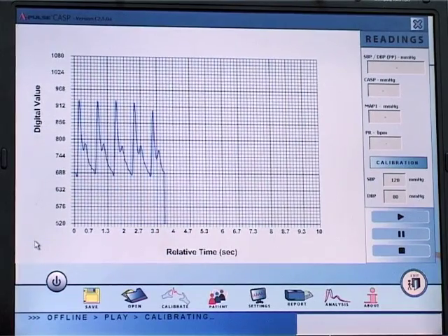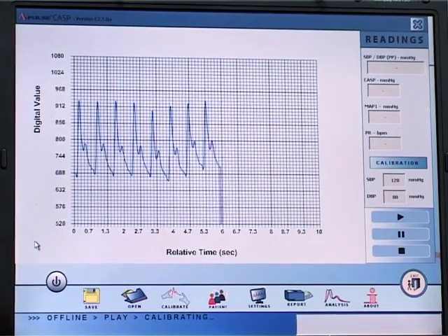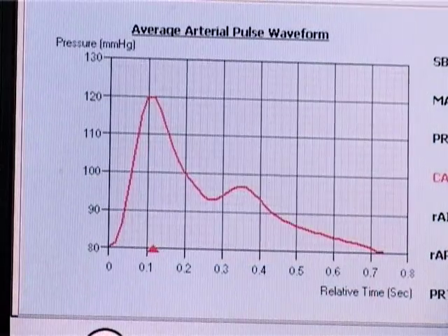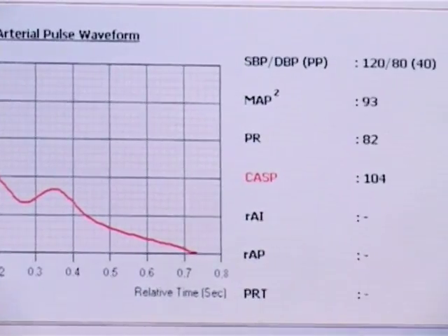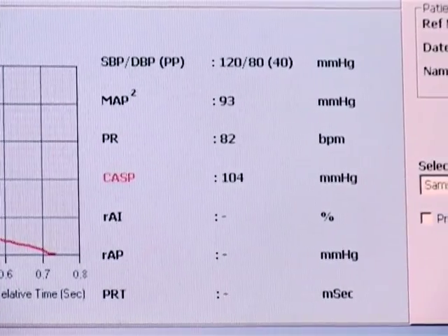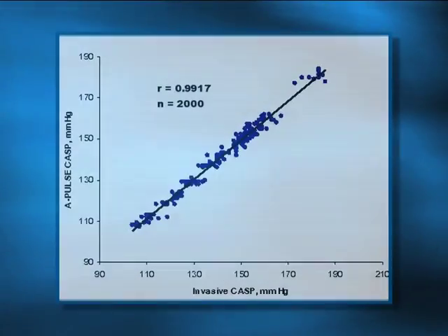When we did the invasive method, using a protocol written by Professor Brian Williams, he used a catheter and put it at the root of the aorta, and we put the B-Pro on the hand of the patient undergoing angiogram. For every wave, we continuously followed wave for wave. We measured the central pressure here, and we read off the central pressure as calculated by the software.